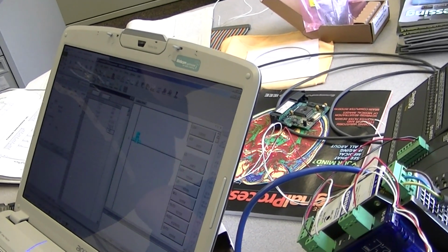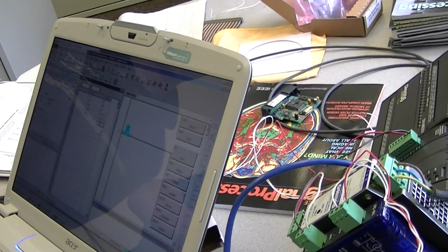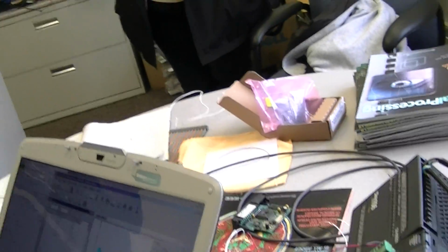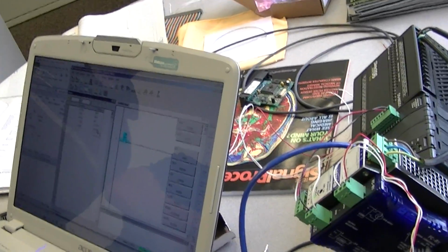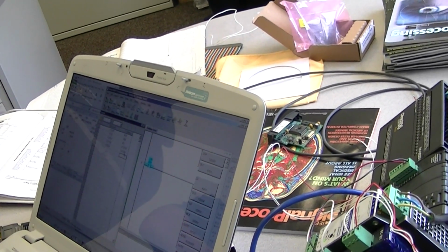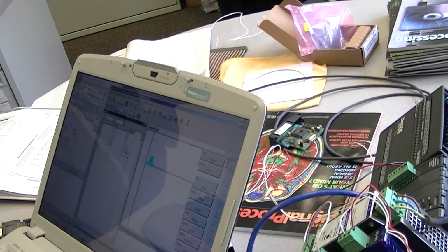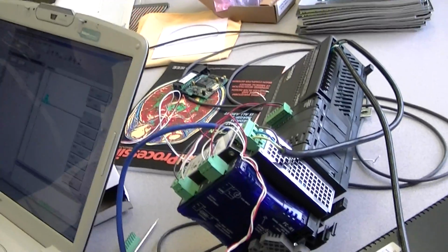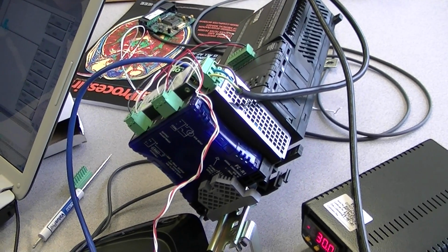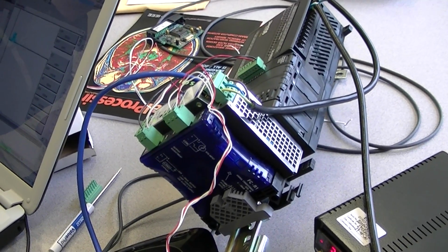Okay. That's not good. So what do I do? Well, I got two choices. It could be that this 12 degree difference, for all temperatures, this thing's always off by 12 degrees. If that's the case, I can fix that inside the computer, no problem. A worst case would be as I change different temperatures, it's off by different amounts. I can take care of that too with a line equation. But okay, if it's linear.